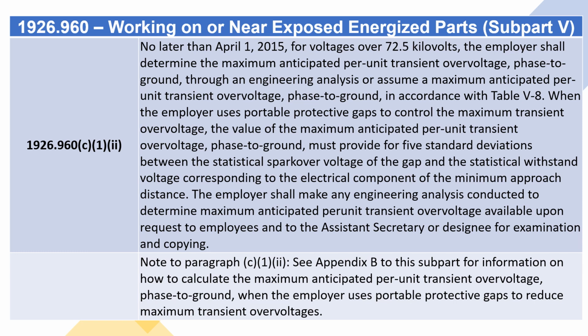When the employer uses portable protective gaps to control the maximum transient overvoltage, the value of the maximum anticipated per-unit transient overvoltage, phase to ground, must provide for 5 standard deviations between the statistical spark overvoltage of the gap and the statistical withstand voltage corresponding to the electrical component of the minimum approach distance. The employer shall make any engineering analysis conducted to determine maximum anticipated per-unit transient overvoltage available upon request to employees and to the Assistant Secretary or designee for examination and copying. Note to paragraph (c)(1)(ii): See Appendix B to this subpart for information on how to calculate the maximum anticipated per-unit transient overvoltage, phase to ground, when the employer uses portable protective gaps to reduce maximum transient overvoltages.